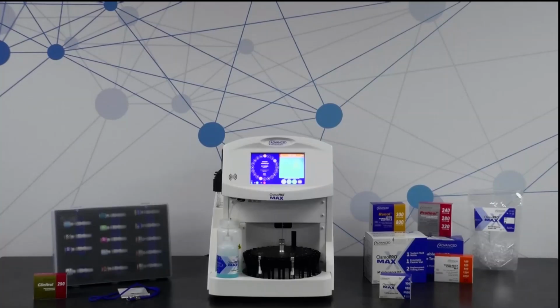But what's cool about this instrument, for example, for that 500 test maintenance, is once you scan in the kit and you initiate the process, there's actually step-by-step video instructions on board the instrument. Again, for the purposes of this demo, I couldn't go through and show you that, but I am developing a little video that will be ready very soon that I can send to those who are interested so you can actually see how this process is carried out. But it does make it really, really easy. So it will tell you with pictures, step-by-step, frame-by-frame, which step you should be doing, how to do it, how certain things should be positioned within the cover, on the tube holder on the side of the instrument, and so forth. So it is super easy to change between 500 tests. It shouldn't take any tech more than about 10 minutes to do the whole thing, leading up to the enzymatic cleaner. Once you run the enzymatic cleaner through the instrument, that process itself takes about 15 to 20 minutes just to make sure everything's cleared out, and then you're good to go.